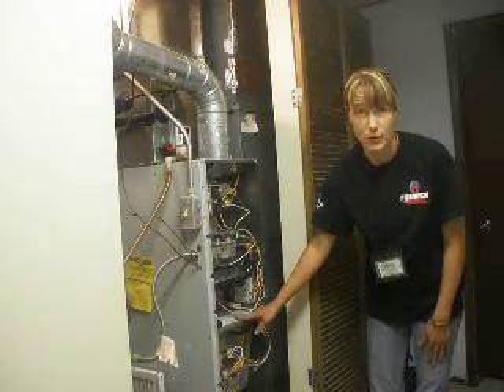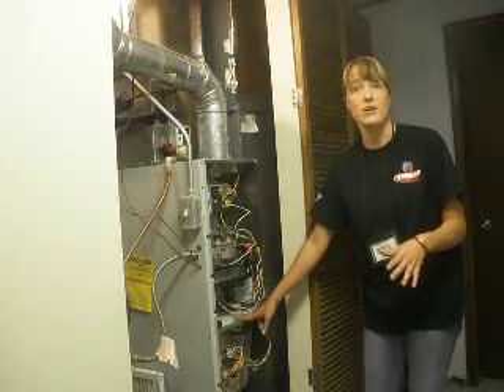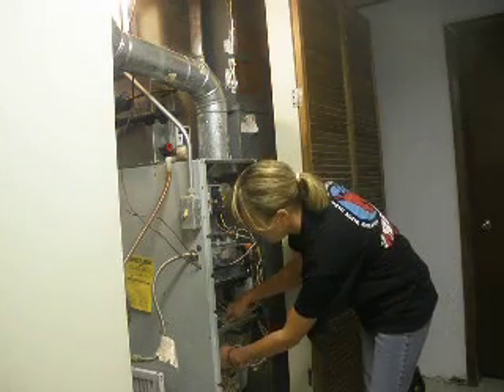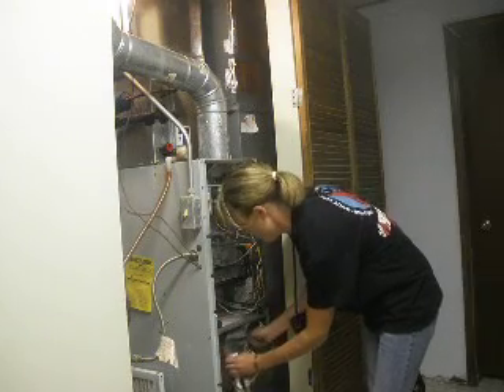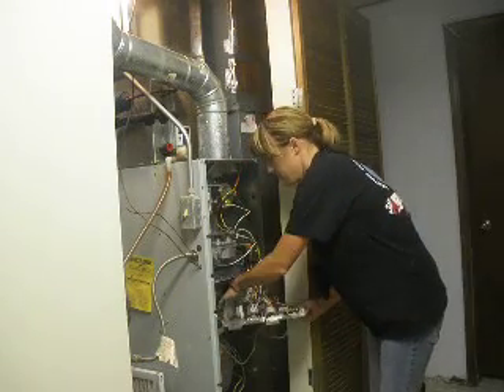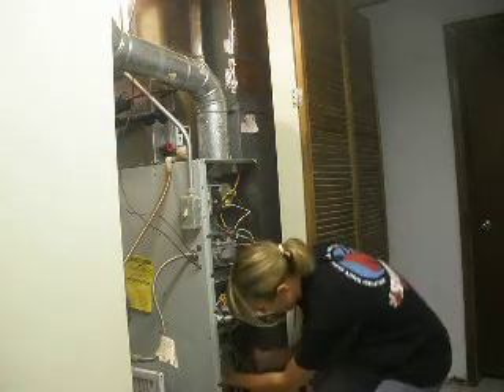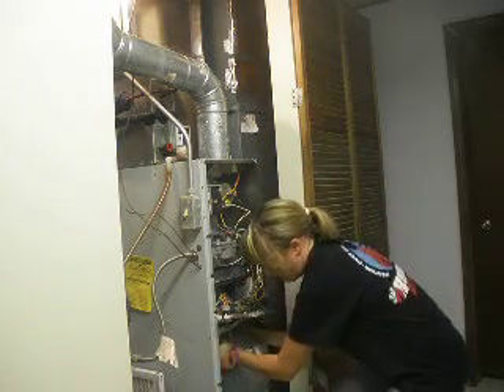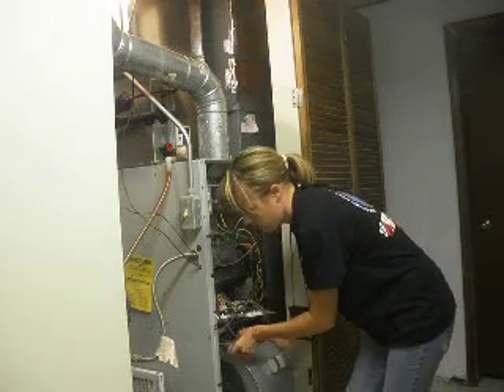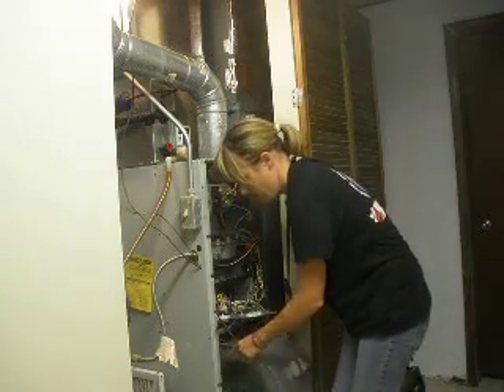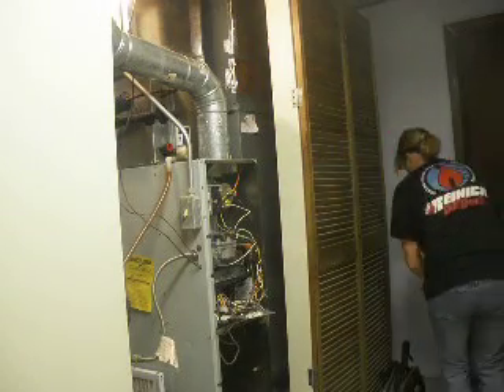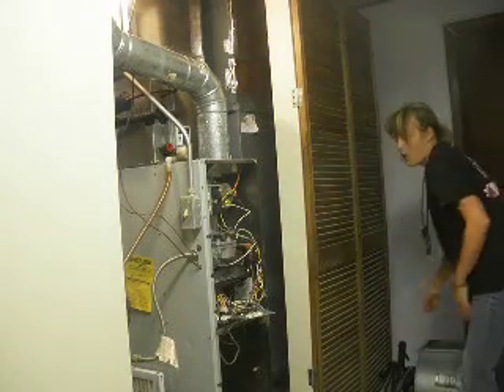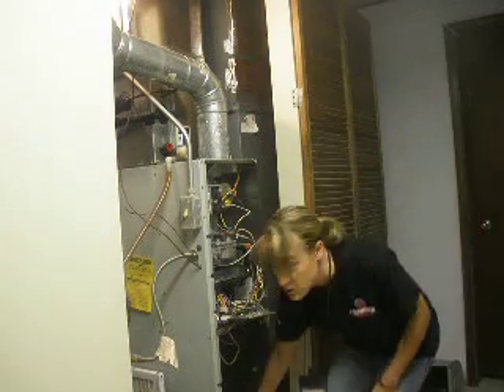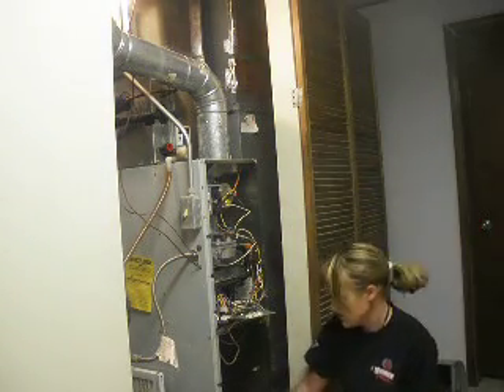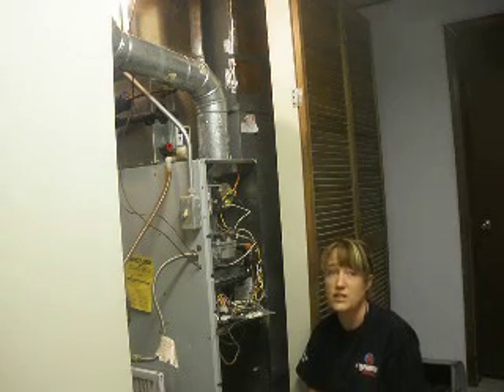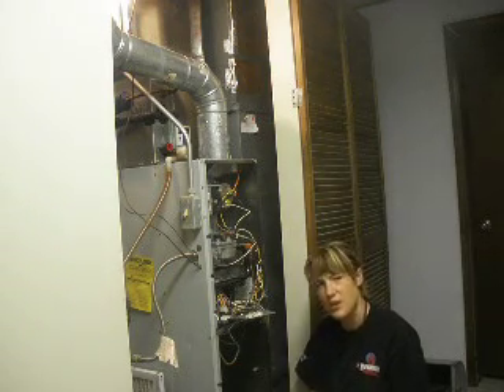Now I'm going to remove the blower, which is going to be taken outdoors and cleaned with compressed air and brushes. I have to do that by moving the logic center out of the way. Going to remove your blower. Set this off to the side here. Now with the blower out of the way, I will be able to visually inspect the heat exchanger from underneath here for any defects like cracks, holes, any rust indicators.